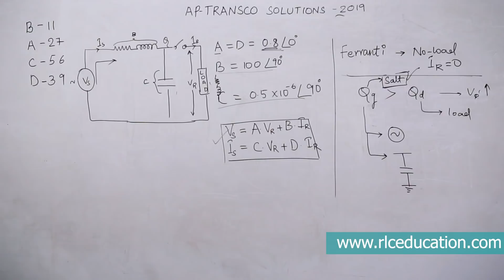Shunt reactor compensation means: since you don't want to switch on the load, whatever may be the reason, but at the same time you don't want the voltage to go beyond limits, I connect some other load, a reactor, which is an inductor, to consume the reactive power. This is shunt reactor compensation for the Ferranti effect, under no load condition, when the reactive power in the line is excess.